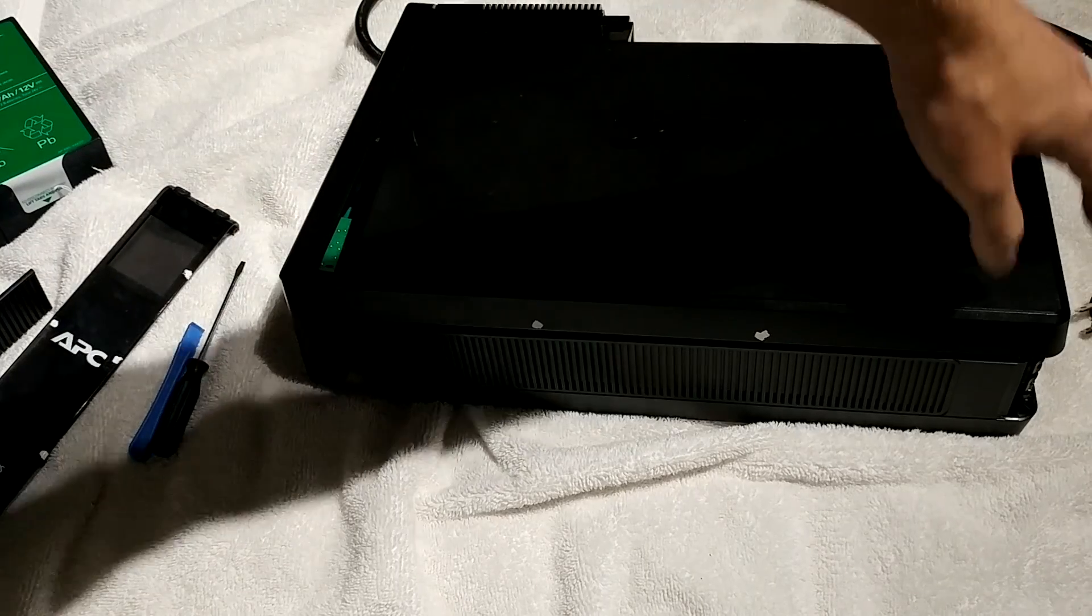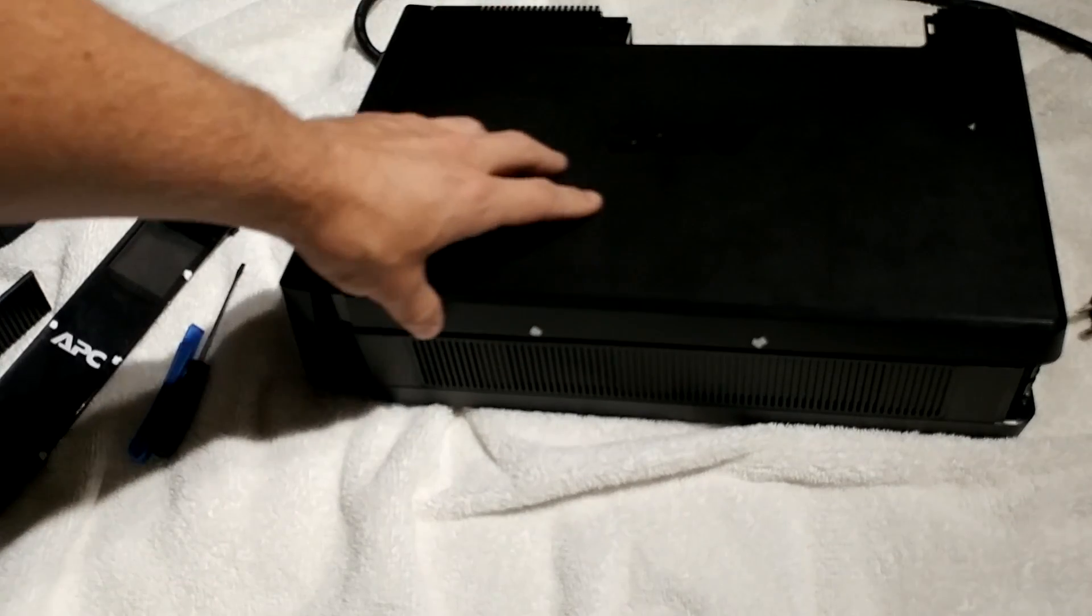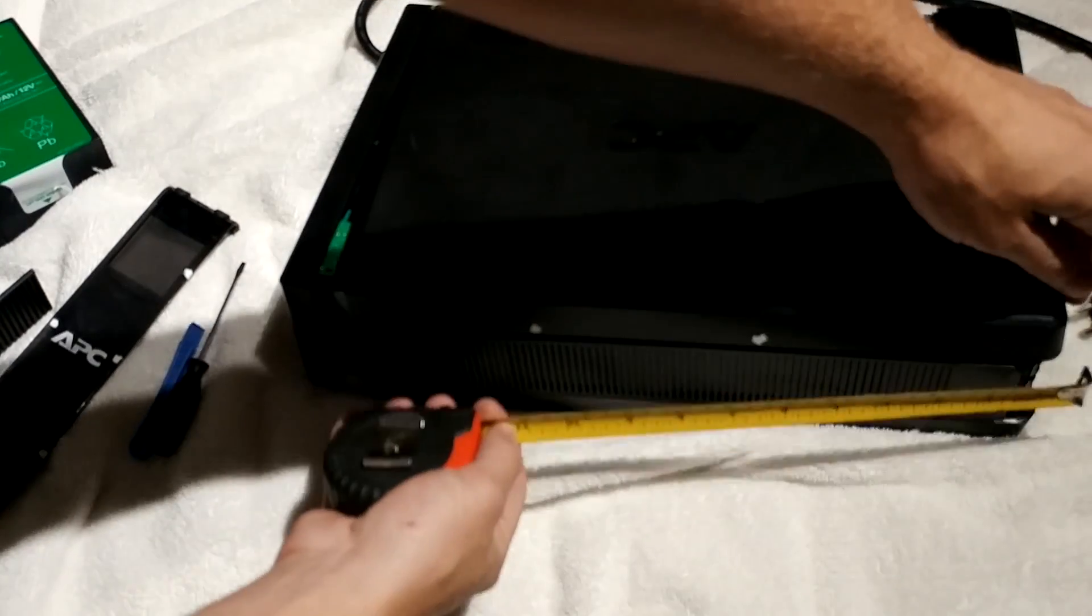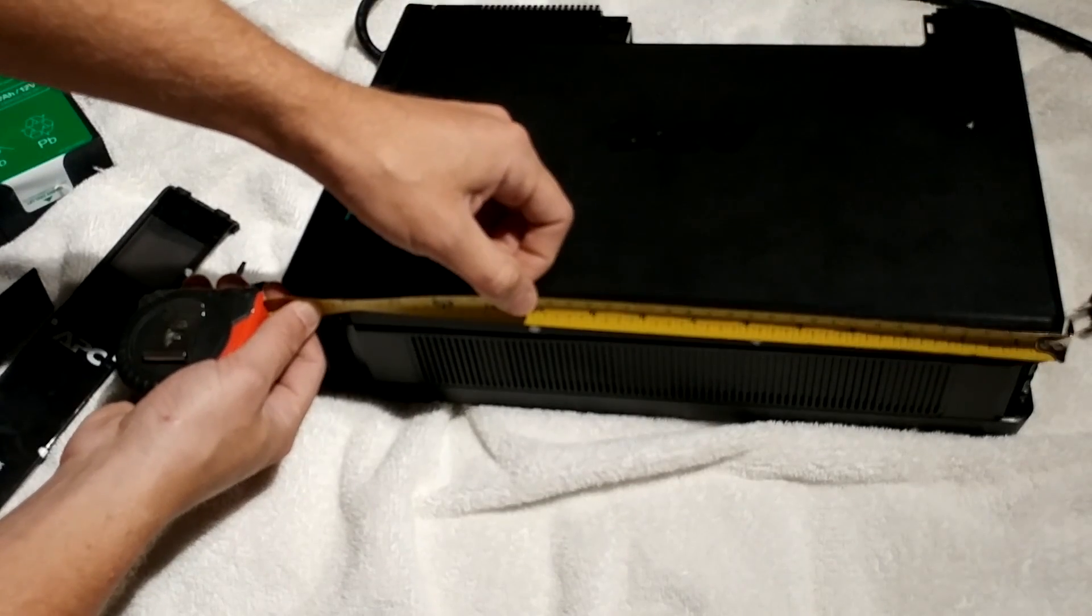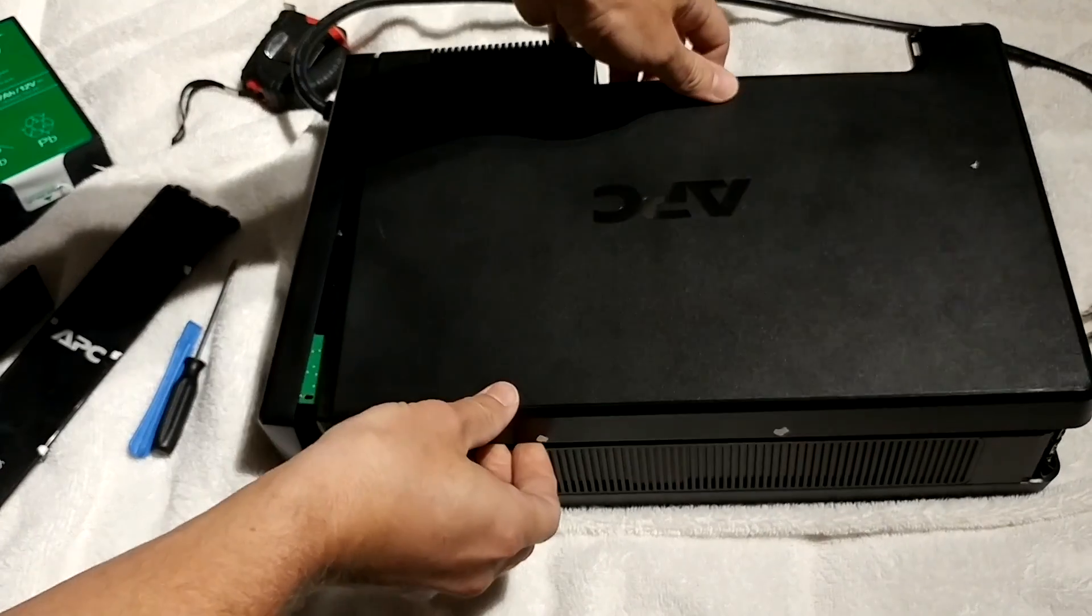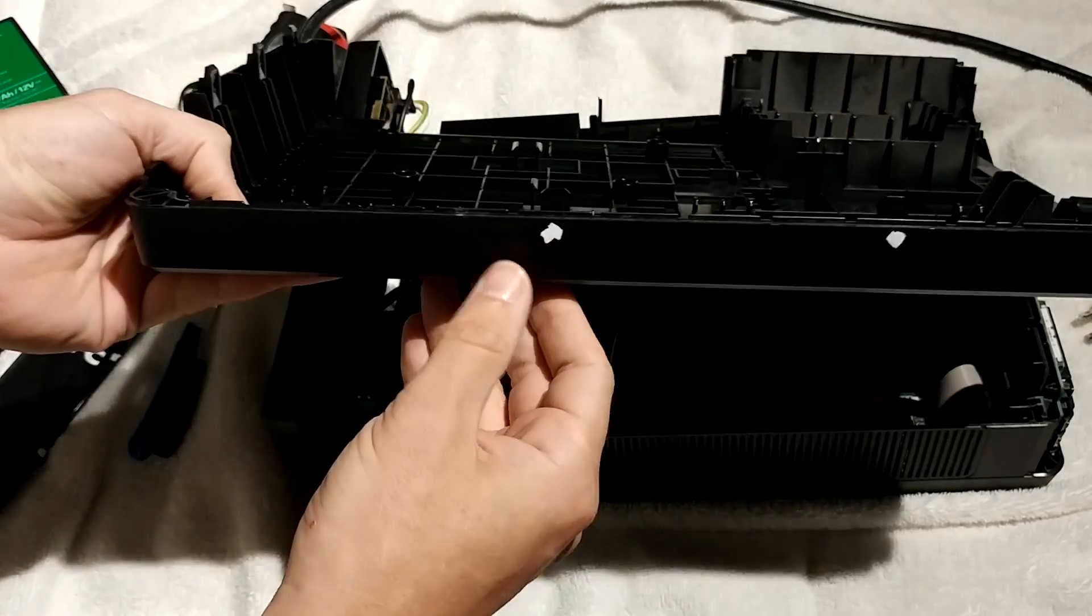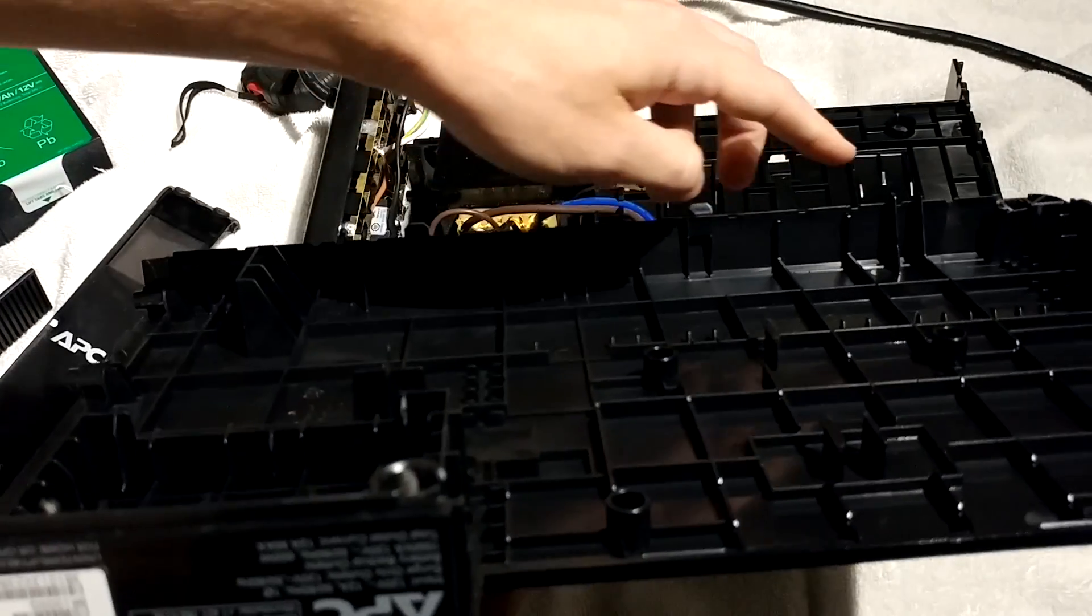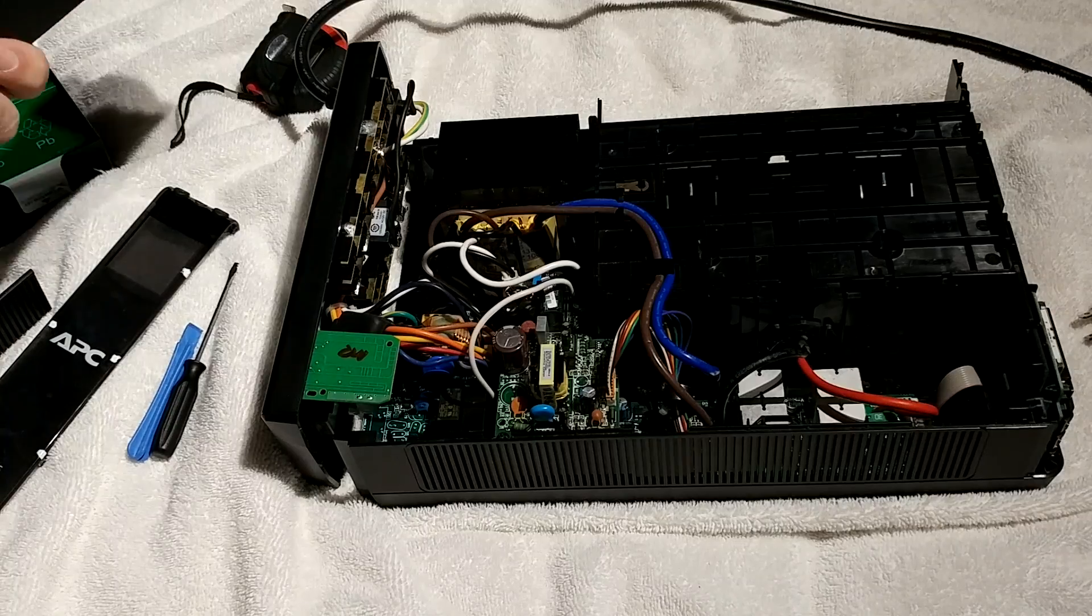Once you've removed the four screws on the front, the whole thing is about ready to come off. The only thing holding this side panel on to the rest of the frame are two plastic retainer clips along the top of the unit. I've marked mine here with a whiteout pen. From the front of the unit, the first one is about five and three quarters, and the next one's about 10 and a quarter inches from the front. What you're going to want to do is lift from the bottom of the unit carefully, and the whole thing should just kind of pry off. These plastic clips are holding the top of the unit together. So once you've got those free, you're inside your UPS.